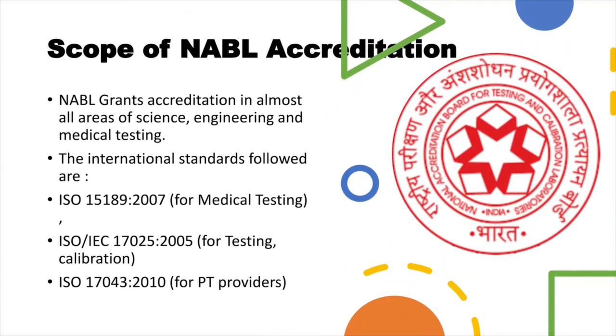The scope of NABL accreditation covers almost all areas of science, engineering, and medical testing. The international standards followed are: for medical testing, ISO 15189:2007; for testing and calibration, ISO/IEC 17025:2005; and for proficiency testing providers, ISO 17043:2010. These are the different sets of guidelines established at the global level which have been tested for different kinds of laboratories.